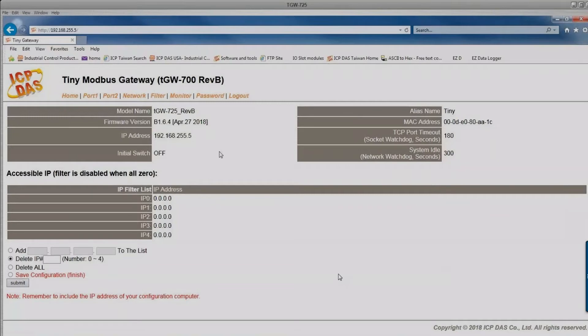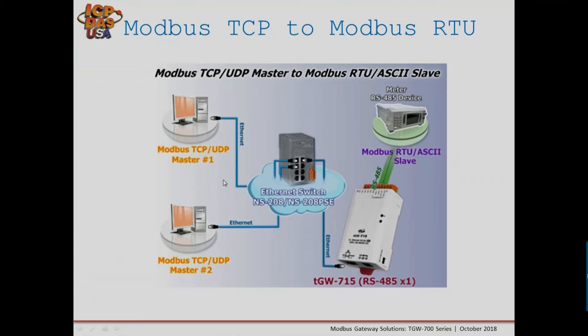To summarize the Modbus TCP to Modbus RTU configuration: set the IP address for the module, COM1 devices are accessed through TCP port 502, and set the baud rate and parity options within the web page to match your slave devices.